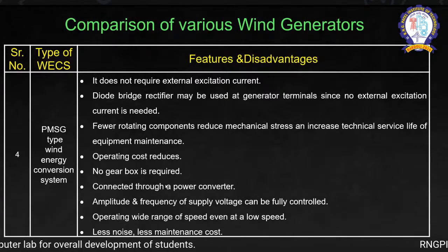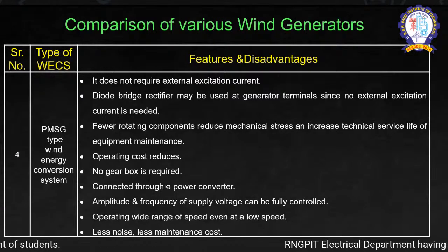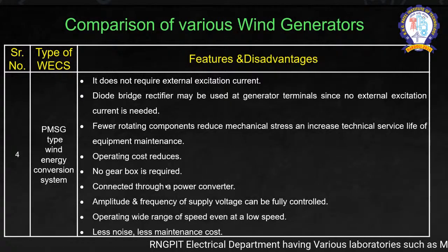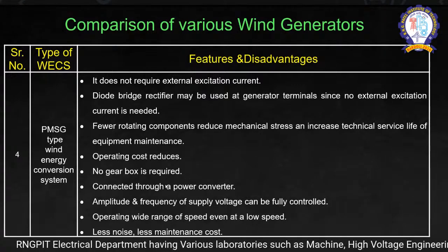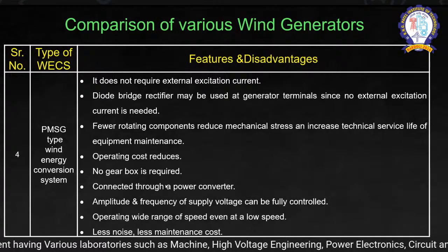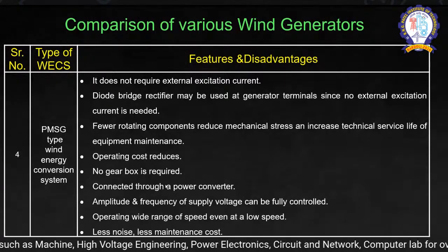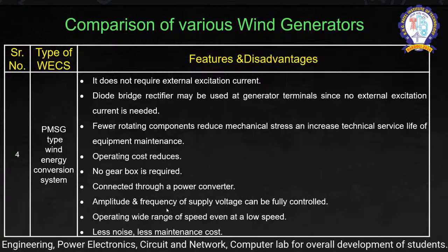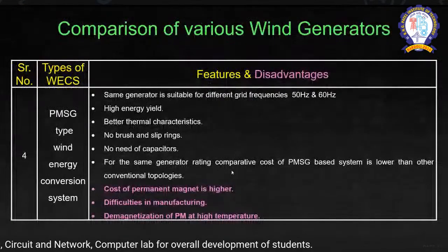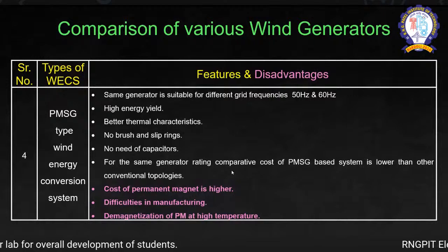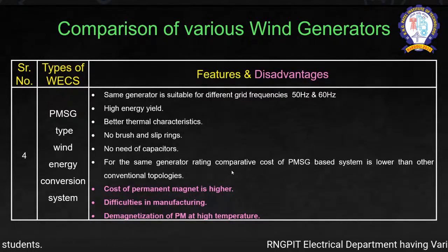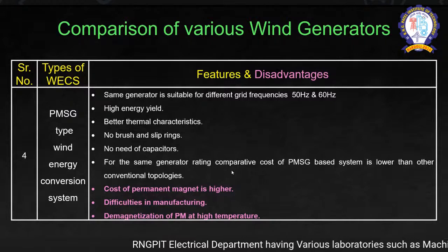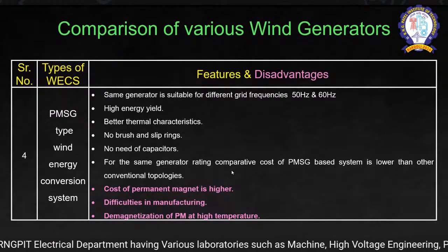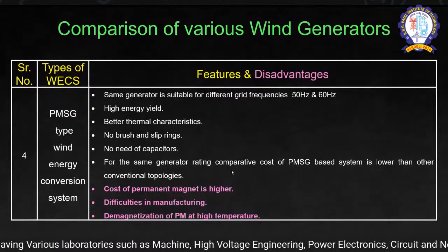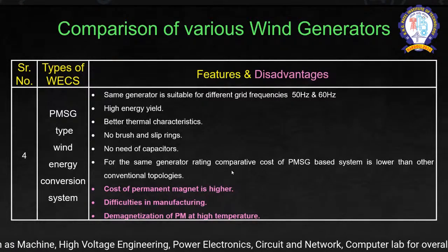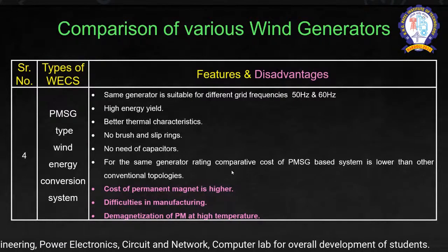So in the ultimate case, we have various aspects of a diode bridge rectifier. It may be used at the generator terminals. Fewer rotating components are there. No gearbox, so the cost has been reduced. The amplitude and frequency of the supply voltage can be controlled. It creates less noise and pollution. The disadvantages are the cost and difficulty of manufacturing. And if you install this kind of PMSG concept at a large scale, demagnetization of the permanent magnet at high temperature might be a problem, as has been observed.